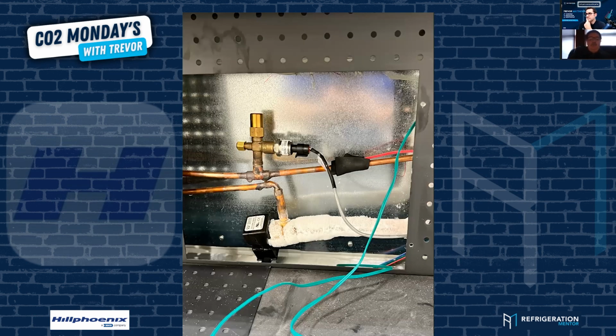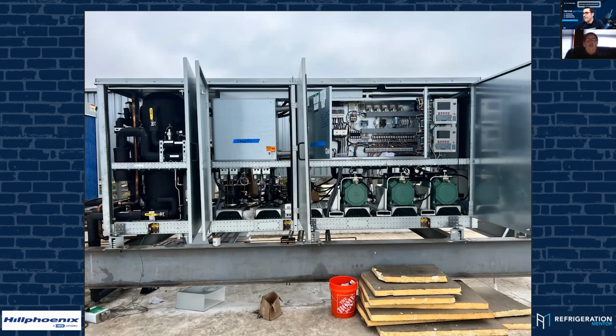All right, so what we have here is a valve that is obviously having an issue. Is that a Danfoss? I can't see. It looks like a Sporlan. So the Sporlan, I haven't had one of them apart, but I'm almost guessing there's probably a strainer in here. On a Danfoss, you'll have to take the top of the valve off, and there'll be a conical strainer inside. And I would look at something in there is clogged up. Yeah, something you want to check. And this is important. This is a valve, not a manufacturer, not a Hill issue. This is a valve. What's going on? Why is it plugged up? Is it dirty? Have you been purging with nitrogen when you put this door in? Exactly. All right, so this is actually a Sprouts job.